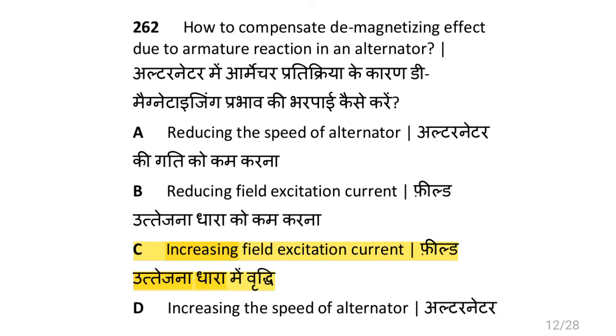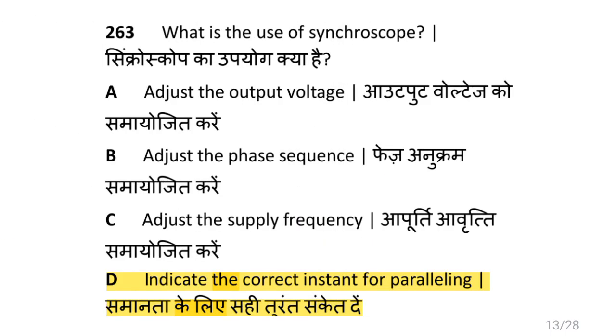How to compensate the demagnetizing effect due to armature reaction in an alternator, i.e. by increasing field excitation current? What is the purpose or use of a synchronoscope, i.e. to indicate the correct instant for paralleling?